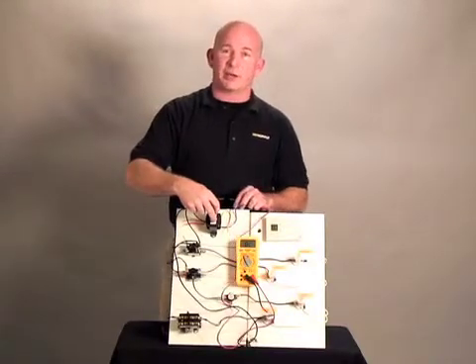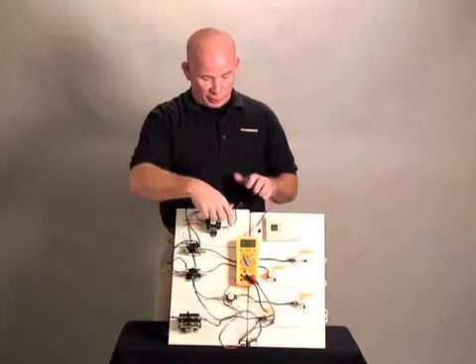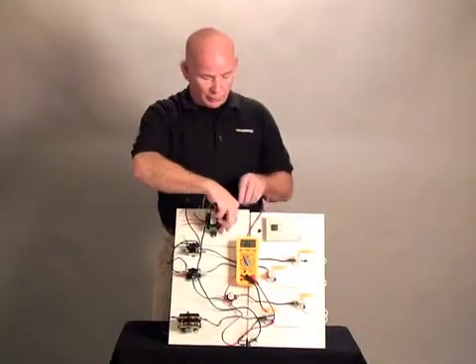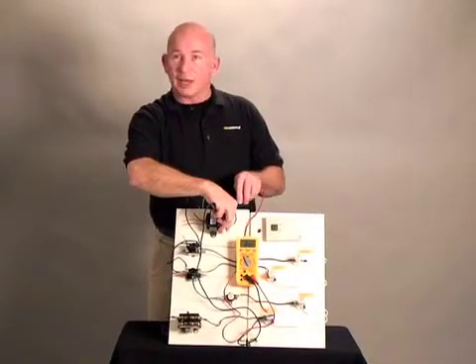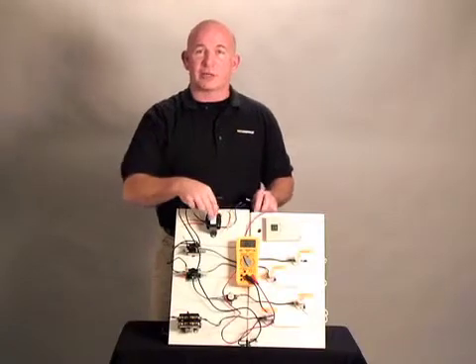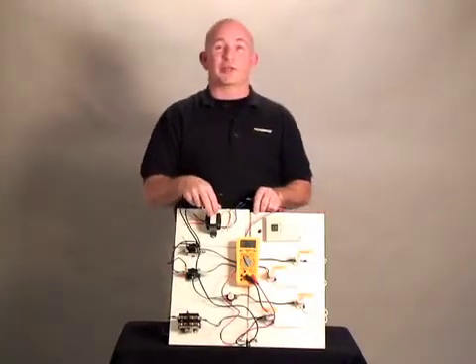To test the secondary side, which is typically 24 volts, you would do the same thing. You would test your blue to your yellow wire and we have continuity. This shows us that the transformer is good.